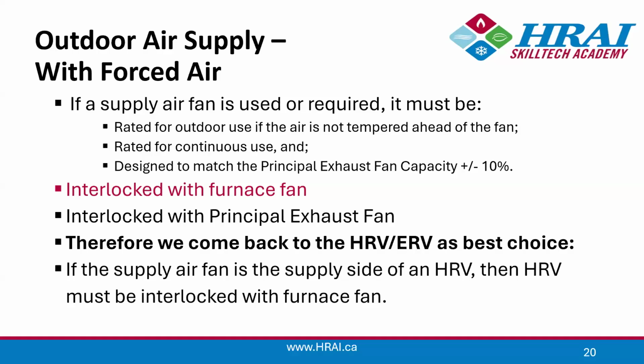So if the supply air fan is the supply side of an HRV, then the HRV must be interlocked with the furnace fan. And that really should be in red because that's a new thing. It's always been good engineering practice to connect your HRV and your distribution system, your forced air system, together electrically so that when one calls, the other is moving as well. But it hasn't actually been a code requirement until now. So do make sure if you're designing, get that into your reports, into the comments, so that people don't miss that part because it will be required.